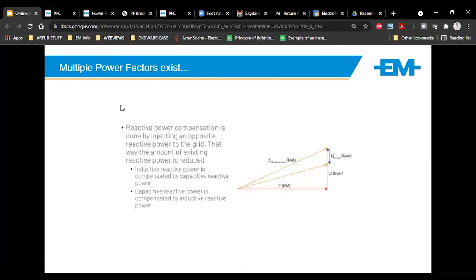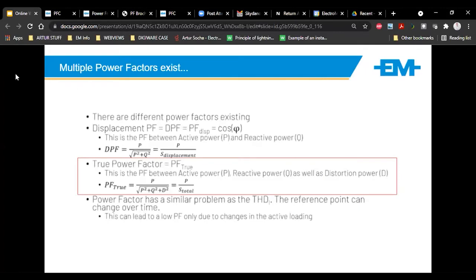Then, quite a topic now: there's more than one type of power factor. A normal inductive load is corrected by a normal power factor system. You have to think of PF in two parts: there's cos phi, and then there's PF. What we normally know, if you just had a motor on a star delta or direct online and you measured that, you'd be measuring the cos phi, which some people call DPF or PF. This must not be confused with true power factor.